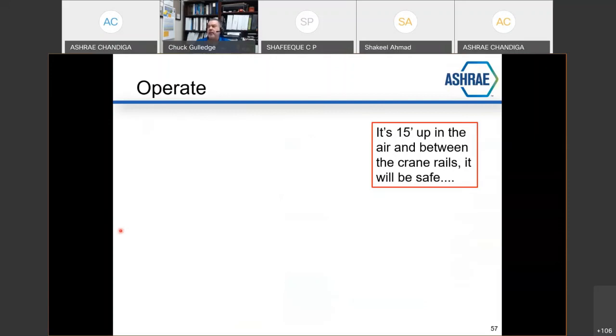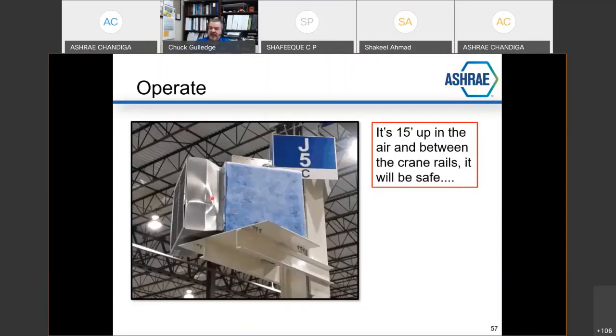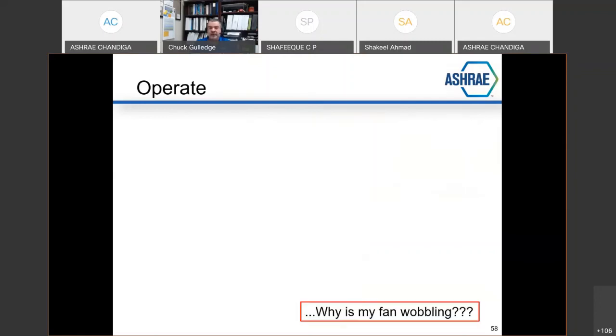It's 15 feet up in the air in between the crane rails. It will be safe. I beg to differ. That is a fan. That is a filter on the inlet. That's the discharge. This platform was 15 feet in the air. The logistical supply team working inside this plant was riding around with their forklifts elevated at high speed, and somebody wasn't paying attention, and they drove a fork right into the side of this. Picture this being oriented. You can see the footprint for where that point right there should have been mounted right here. They hit that with a fork, sheared all of these off and rotated it, and made a big mess, all because of unsafe operation.